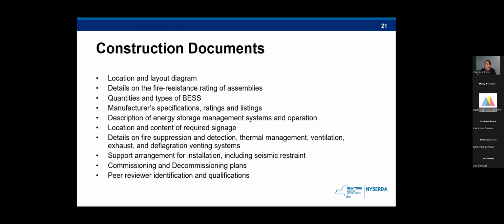And while there is signage required in this fire code, there's also signage that's required as part of the National Electric Code on the electric side, which we won't cover today, but is something else to be aware of. They'll have to provide the details on fire suppression and detection, thermal management, ventilation, exhaust, and venting systems, which we'll get more in depth on as we go through the presentation. The support arrangement for installation, and then the commissioning and decommissioning plans, and if required, the peer reviewer identification and qualifications.